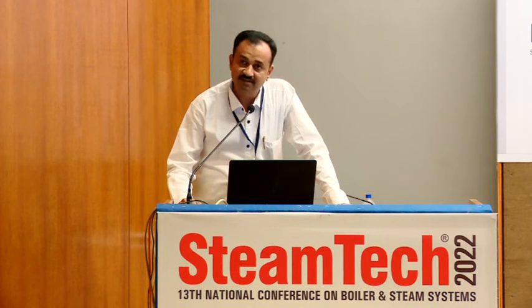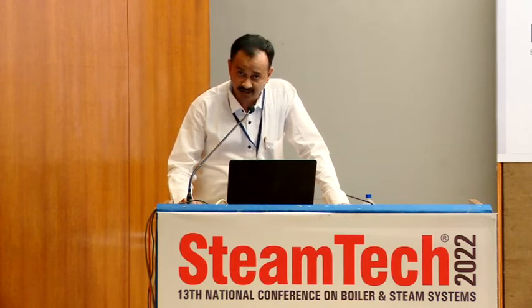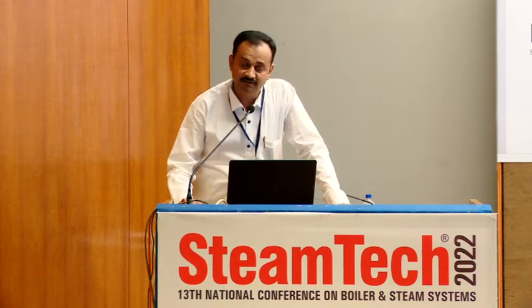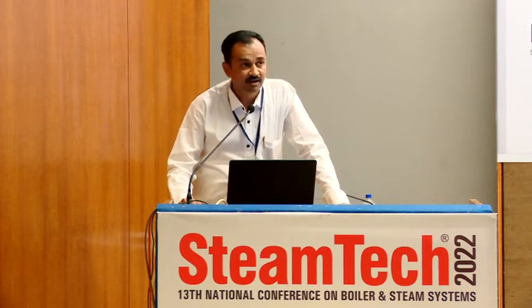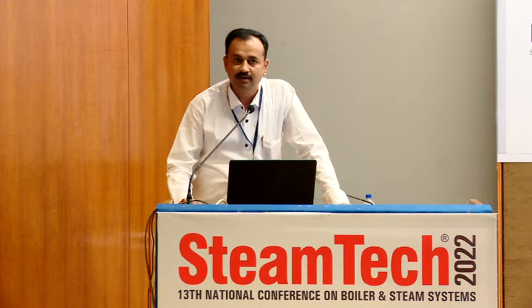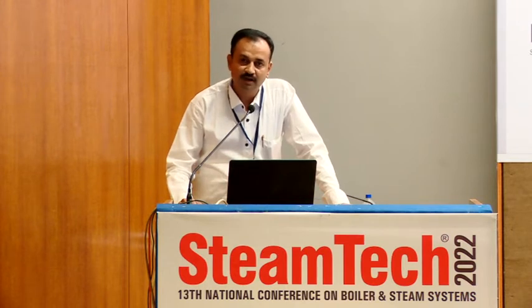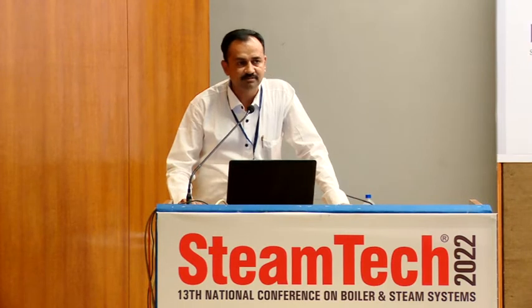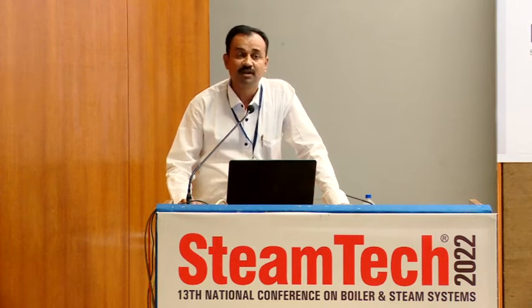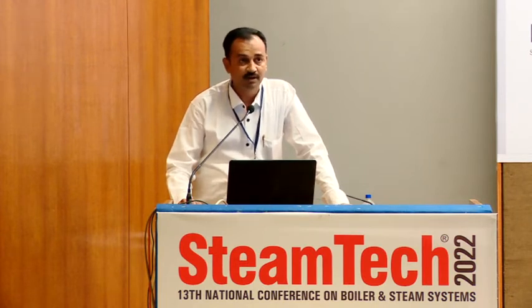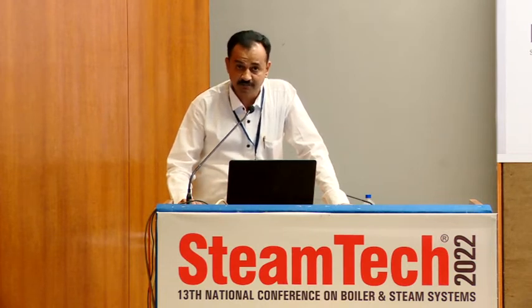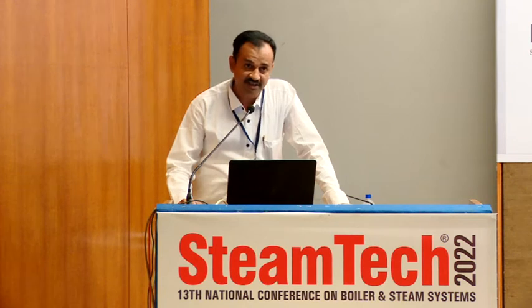With this, predictive analysis will always be available with the connected sites on the cloud, connected boilers on the cloud, and we can identify and further improve that process and operating condition. Now, going into slightly more detail, if we connect the boiler house or the equipment of the boiler house on the cloud, what benefit can we expect? Starting with the specific fuel consumption and specific steam consumption, the steam is going to be utilized in the plant process side, to conserve in the form of steam and in the form of fuel. Also, to identify the best steam pressure, best feed water temperature, and best condensate recovery factor with the diagnostics available with the digitally connected sites.